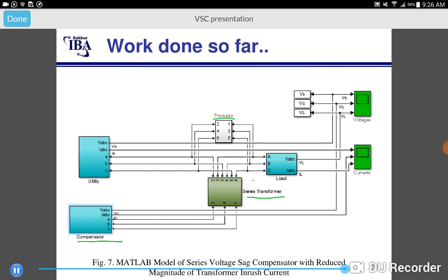At the time when sag occurs at the grid side, the compensator generates the compensated voltage according to the sag detected by the controller. This magnitude of compensated voltage is added with the line voltage via series transformer. The current and voltage ripples of the inverter are filtered through the capacitor and leakage reactance of this transformer. In this manner, the load is supposed to have constant power supply.